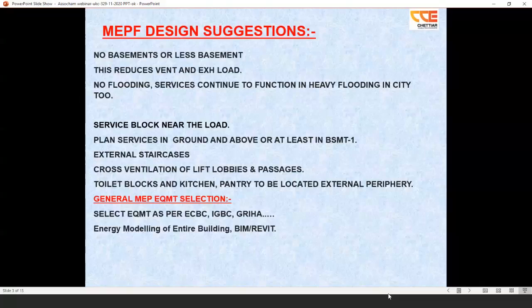That's fine. We have seen many buildings where clients and architects come up with putting the toilet blocks in the middle of the building, which means there's a corridor for the people and the toilets are in the corridor, which again increases the power consumption of the building. You have to put the toilet with mechanical extraction, and you need a bigger shaft and larger floor space for maintenance. So the moment you put the toilet block to the external periphery of the building, including the kitchen and pantry, one thing is that you reduce the shaft dimension.